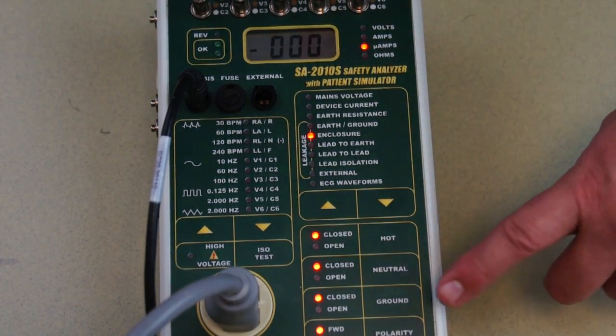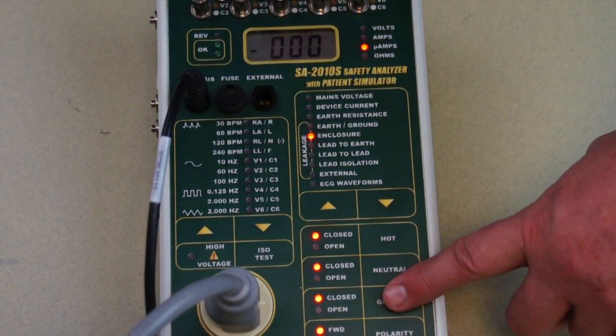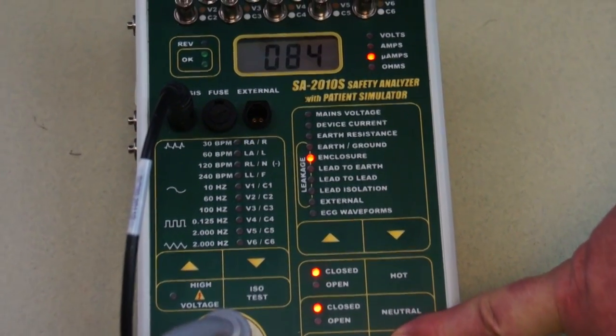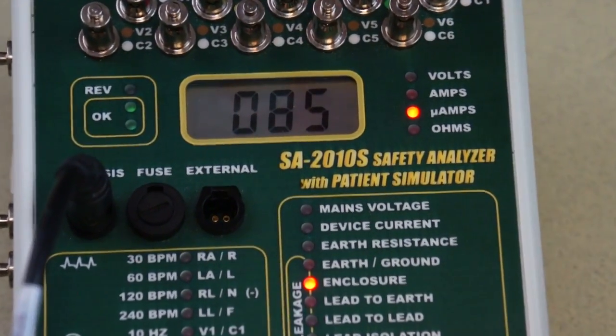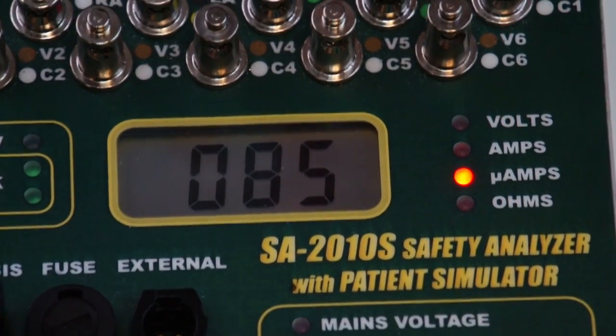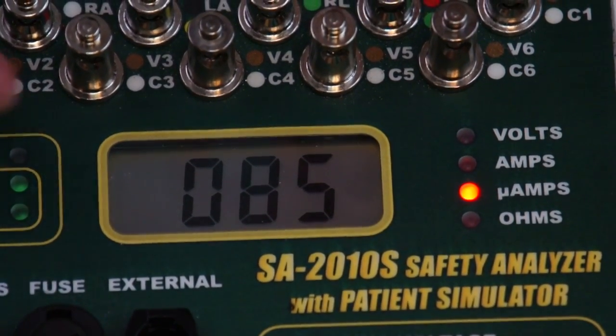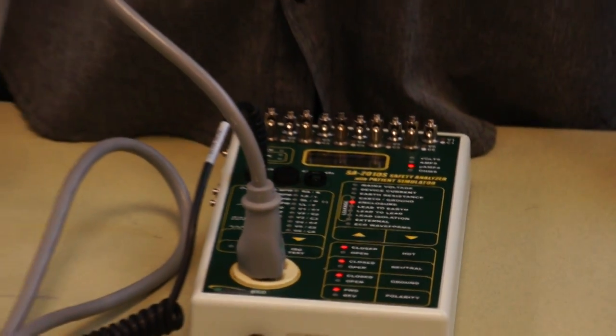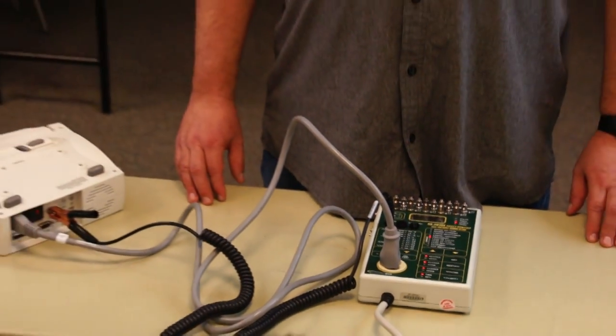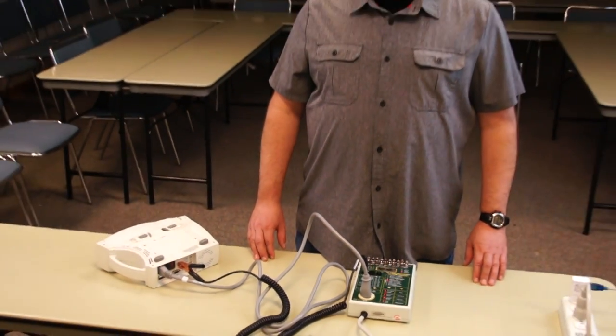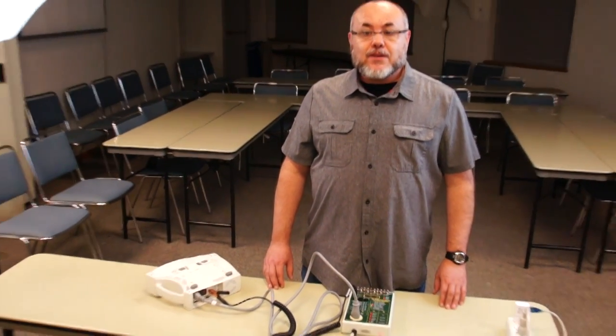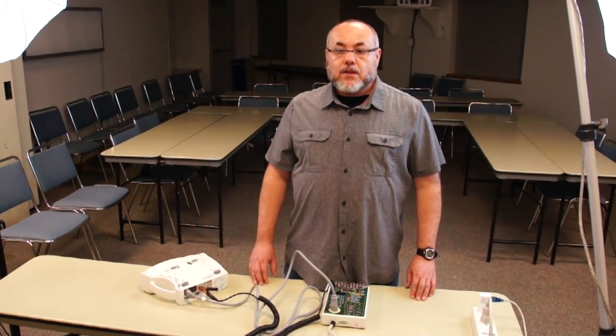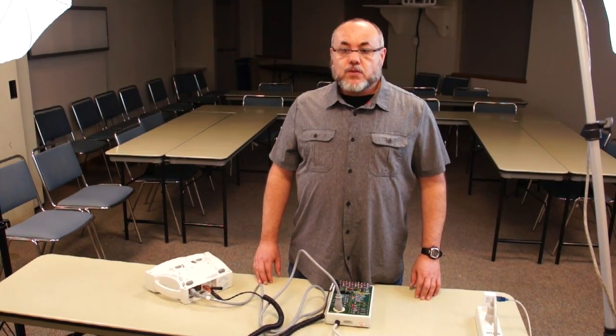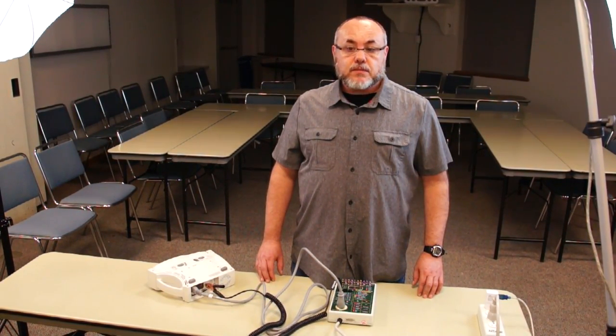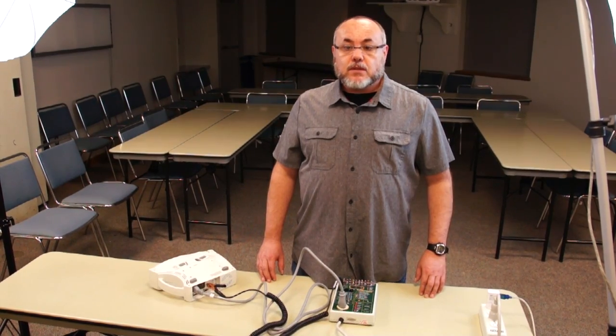When we press and hold the open button, we notice that our leakage current is again at the same value we measured before. This is all that is required for testing a device that has no patient leads. For a defibrillator or an ECG machine, we are going to use the leads, and there's another set of tests that we will perform to do a leakage test on those. But for this device, we are complete.